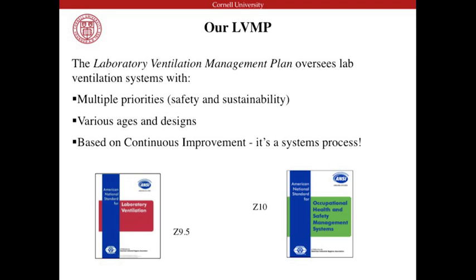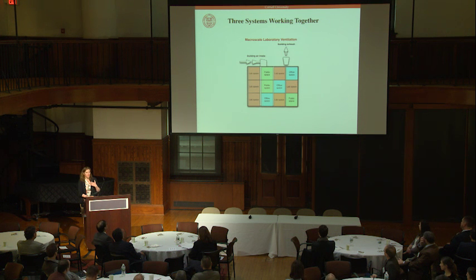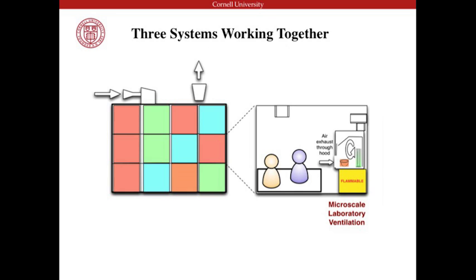We also recognize that there are different layers of the ventilation systems. We have a large campus, and I work at some level of the ventilation system. Mark works at a different level; we have teams of people with different responsibilities for these systems. At the macro level, you have where air comes into the building and the exhaust stacks. Then inside the building you have mixed-use spaces, with pressurization differences between those. Then inside the lab is where the people are working. That's where I come in.